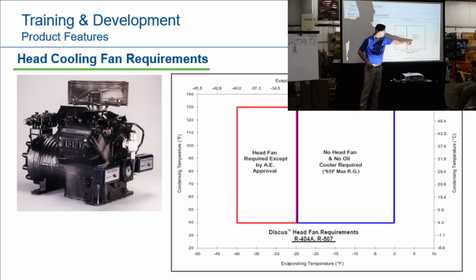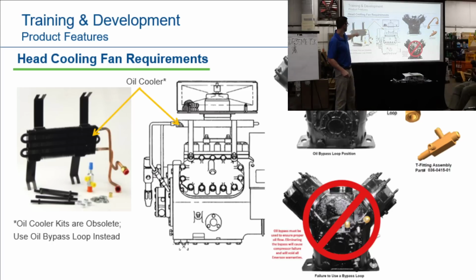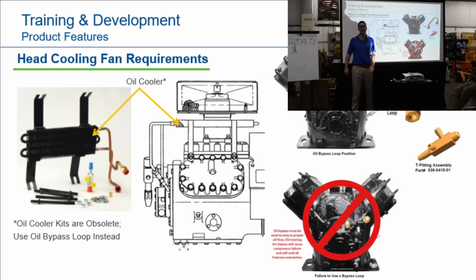When I'm running maximum of 65 degree return gas and I'm running minus 15 and 80, I don't need a head cooling fan with 404 or 507. But here, if I'm running in here, I need a head cooling fan. Make sense? Excellent. Talked about this oil cooler. If you don't have it anymore and it was on the old one, you have to add a bypass loop. Because if you don't and you cap it off like this, you're going to get another failed compressor.